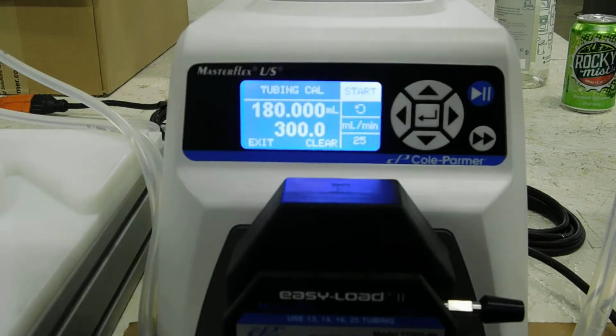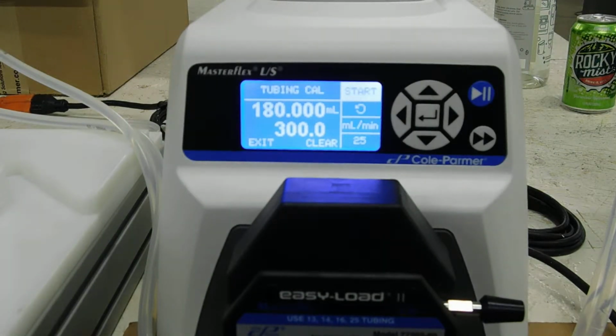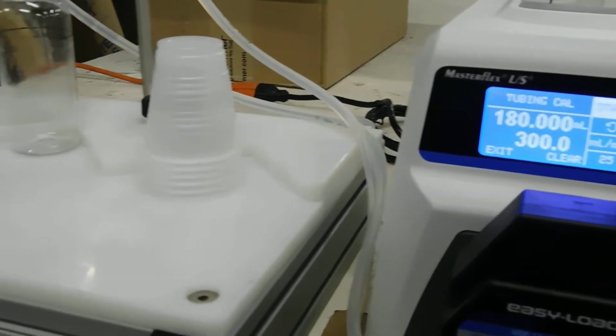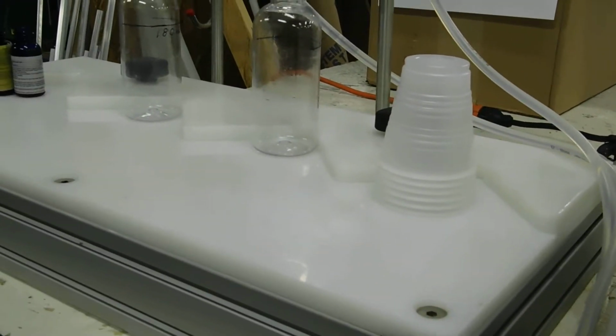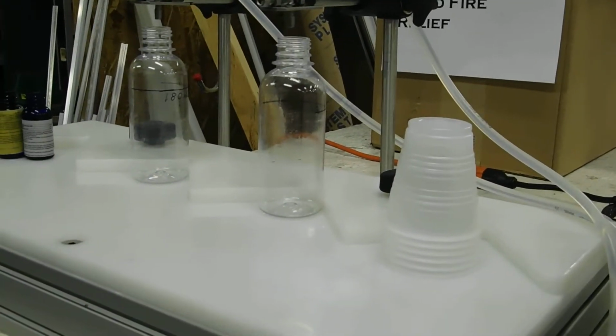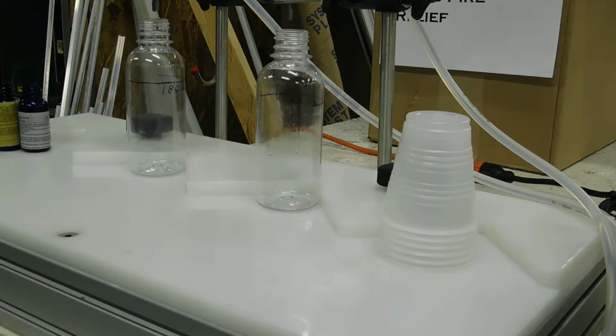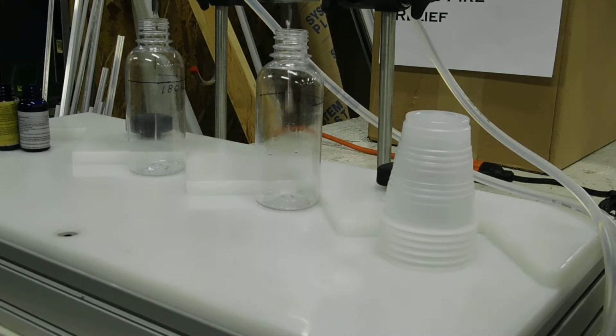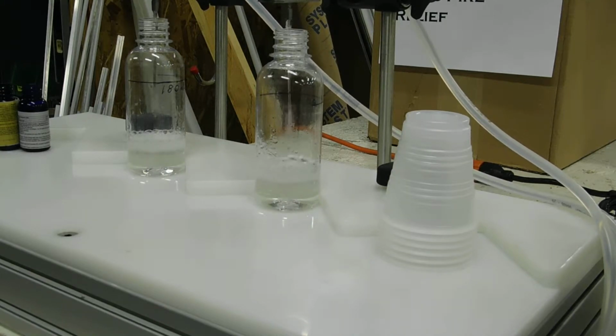to calibrate the tubing. So what I'm going to do is I'm going to dispense into these two other containers here. I'm going to press the foot pedal or press enter on the start screen. What it's going to do is it's going to dispense what it thinks is 180 milliliters of product. And then I'm going to measure the product that it actually dispensed and make a correction.